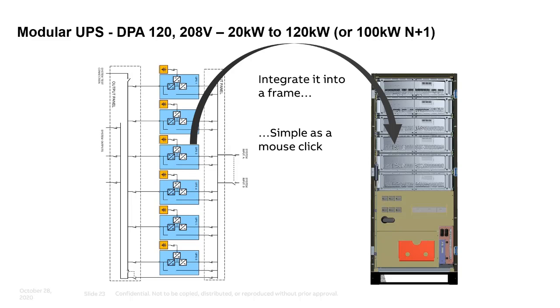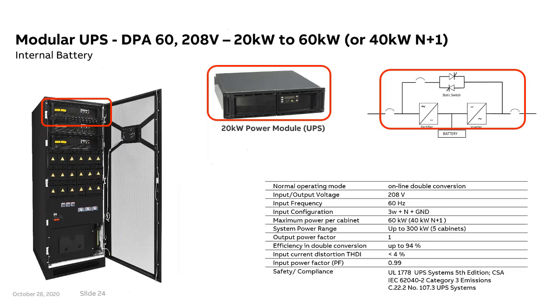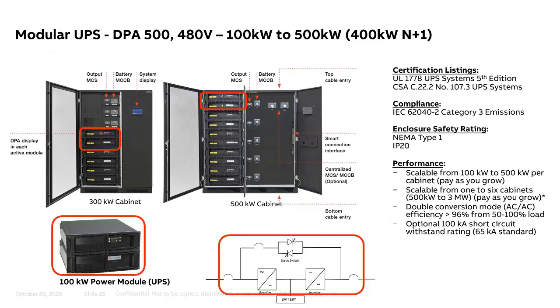In the 120, there's no space for batteries. Batteries will be in an external cabinet, which leads to the next frame based on the same module and actually the same cabinet, but only leaving space for 3 of the 20 kWs, thus the name DPA60. It can support, fully populated, up to 60 kW or 40 kW N+1, but it has space for built-in batteries. Same power module, so exactly the same concept. And if we jump to the 480 volt, the bigger boxes, based on what we see at the bottom here, that 100 kW power module is a full-blown UPS. There are 2 different frames. One will house up to 3 of them, one will house up to 5. And like the other ones, the customer can start with 1 or 2, and they can add more as needed.